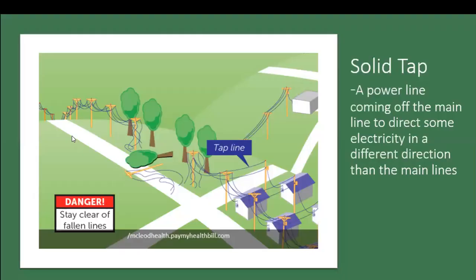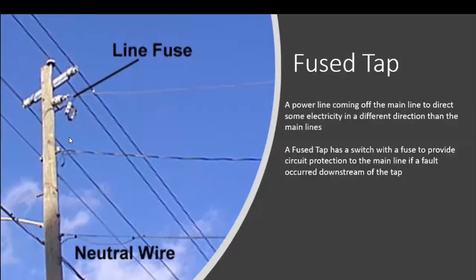They also have what they call a solid tap. Now I'm going to use the previous picture here. If the fuse was not present, and you will find this on some systems, if I took a piece of wire and just connected it from the tap line directly to the primary and didn't include this switch and fuse, that would be a non-fused or a solid tap.